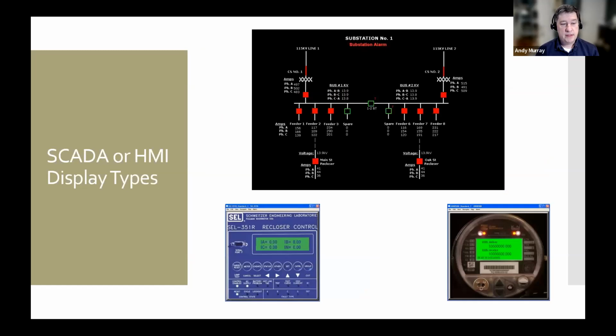So then you have the SCADA or HMI displays. The top display here is the typical display, at least for systems that I design and work with - what we call a one-line display. The terminology comes from the fact that these white lines represent the primary electrical system, which is often 3 wires or a 3-phase system, but it's drawn as one because all 3 wires go into each piece of equipment.